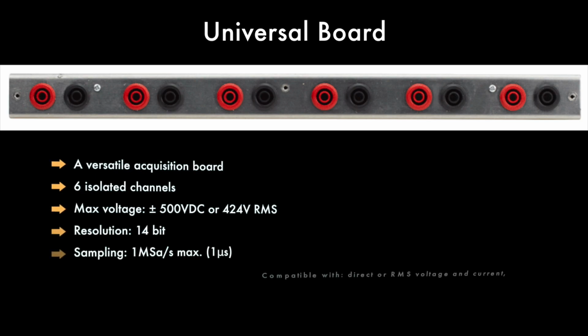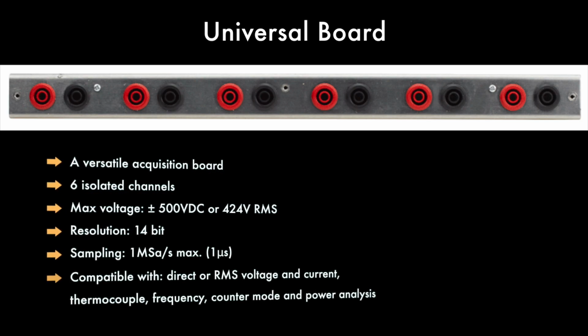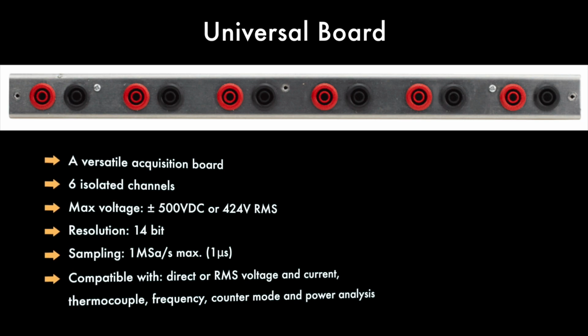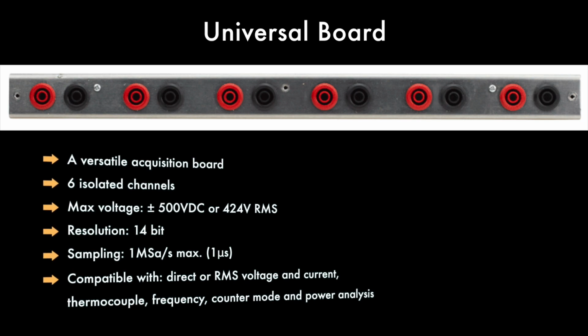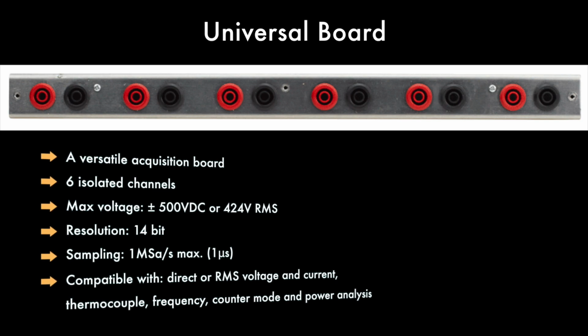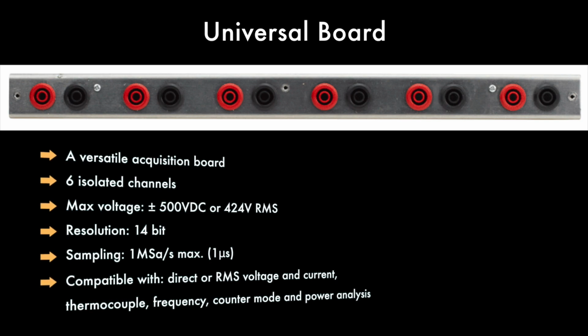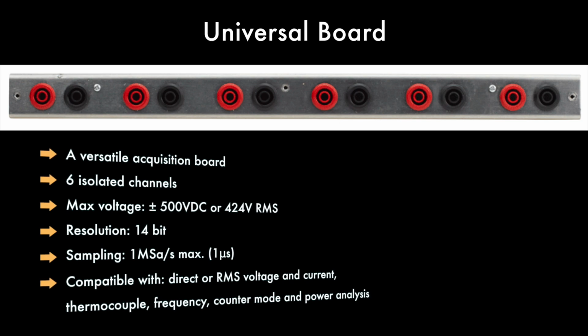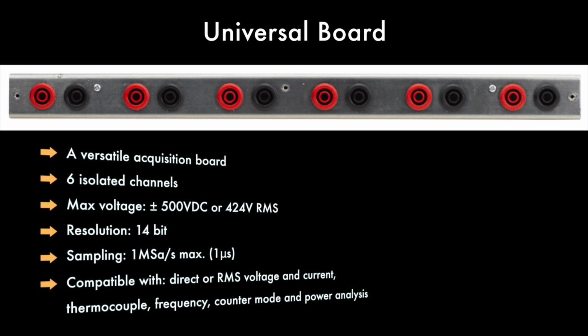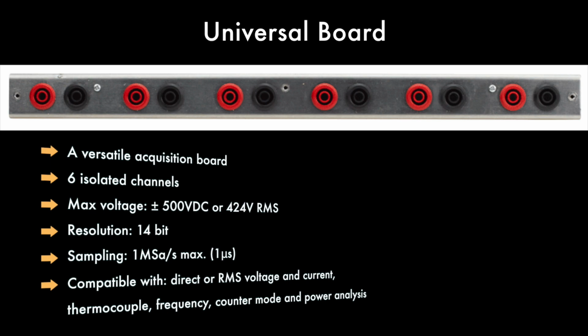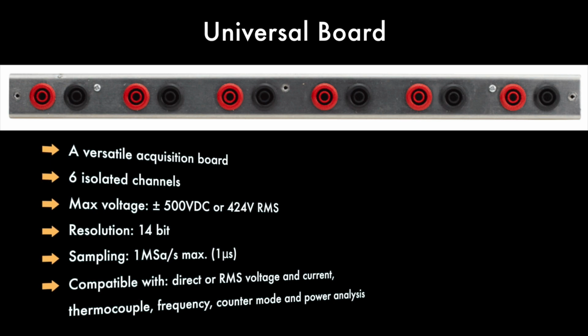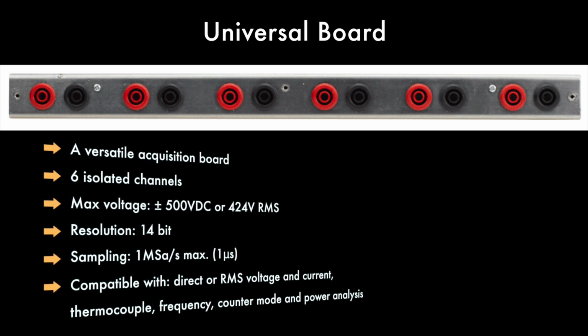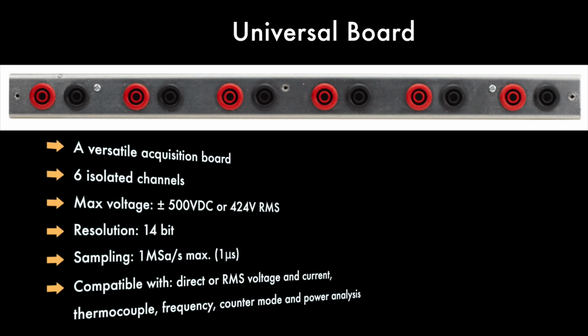It has 6 isolated channels, a maximum voltage input of plus and minus 500 volts, a 14-bit resolution and a maximum sampling rate of 1 megasample per second. This board is compatible with DC or RMS voltage and current recording, frequency, temperature with thermocouple sensors, counter, and power analysis.